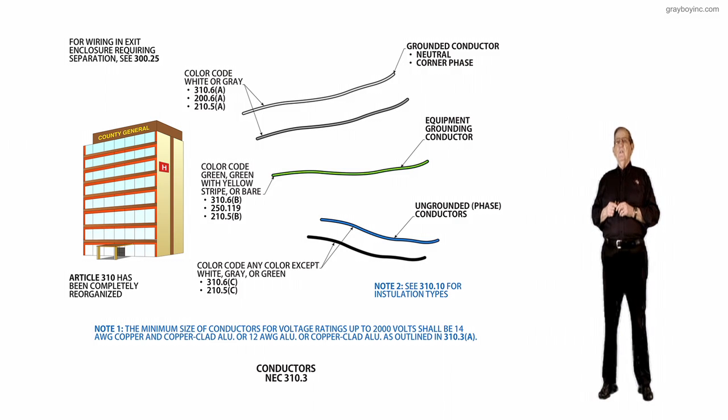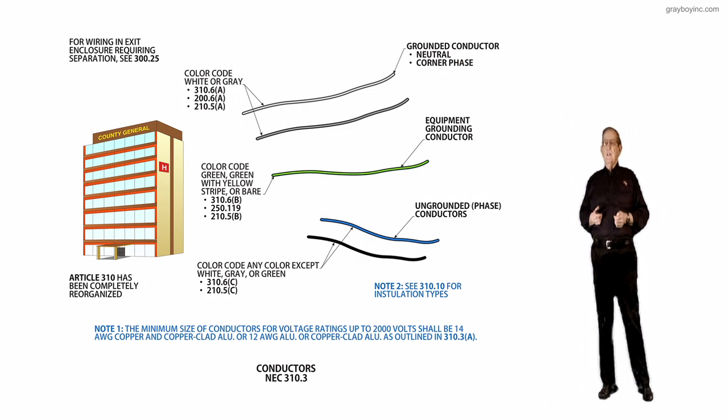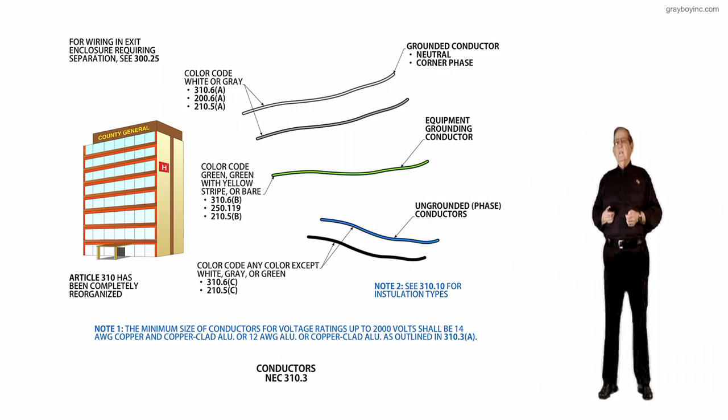And if you look at 310.6(C), it will refer you over to 210.5C for branch circuits, but it would send you for feeders to 215.12C to determine what color you could use on those ungrounded conductors.